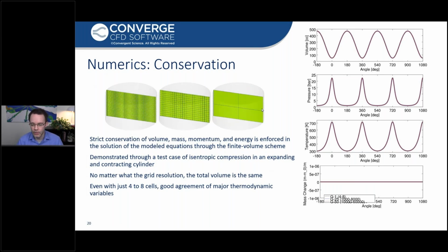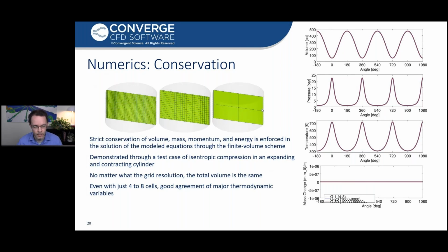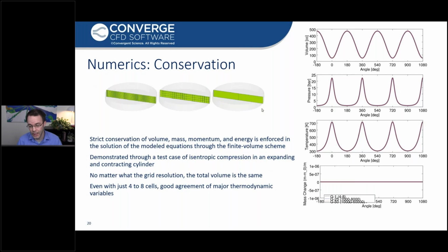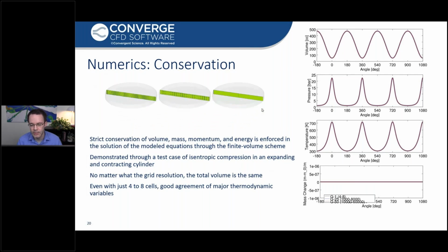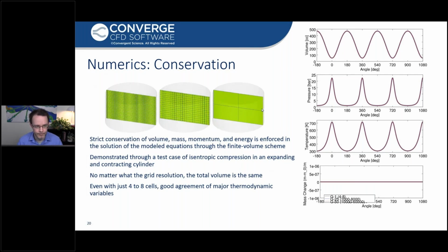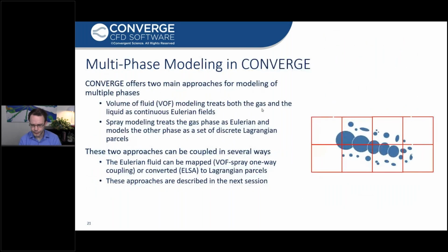So this quality of the numerical method is very important in modeling positive displacement compressors because we want to be sure that no matter how fine or coarse the mesh is in certain places, we'll still have these overall conservation of quantities being satisfied.